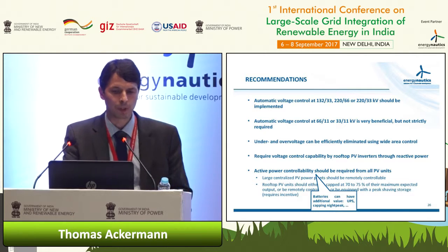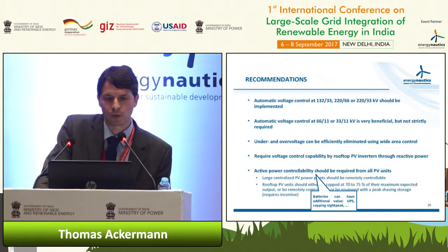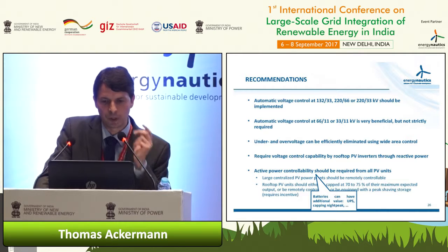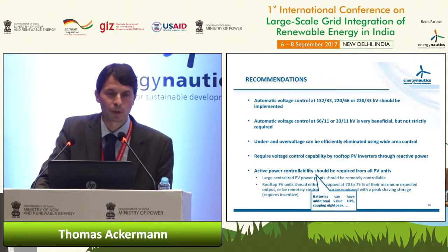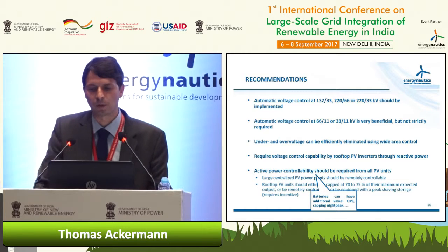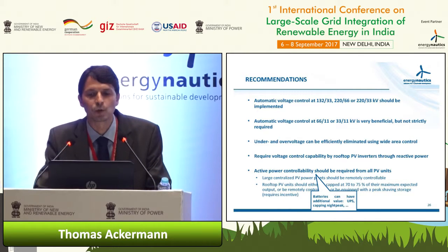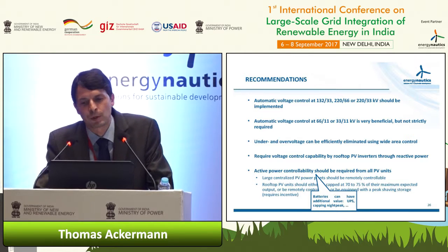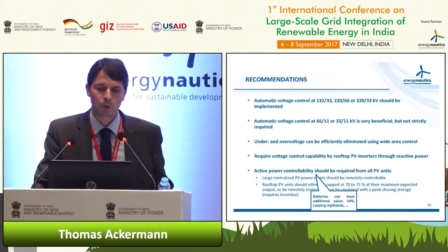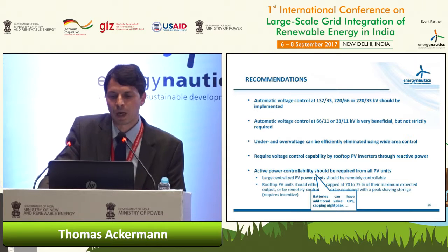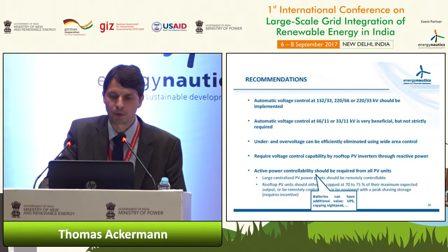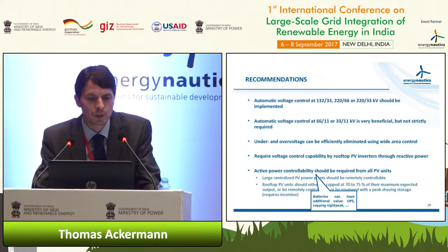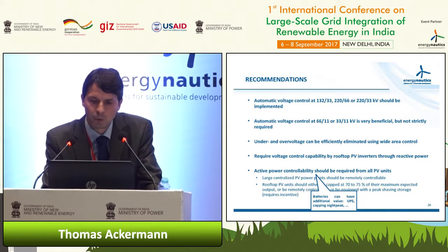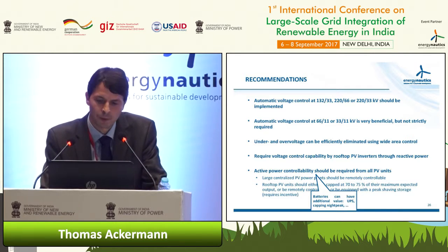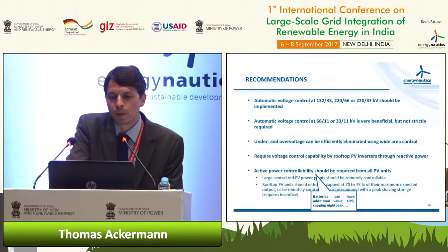Recommendations. We do recommend that automatic voltage control is implemented for the 132 to 33 kV transformers, where currently the on-load tap changing is applied, but it's done manually. So these should be automatic. It would even be beneficial, but not strictly required, to have this also for the power transformer 66/11 to 33/11. Under and overvoltage issues can be efficiently eliminated using wide area control. It's not that expensive.